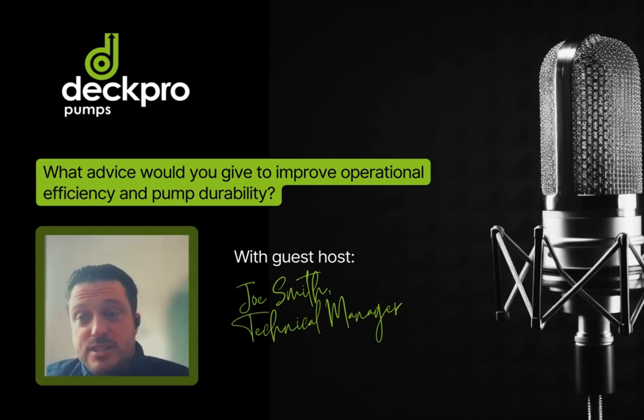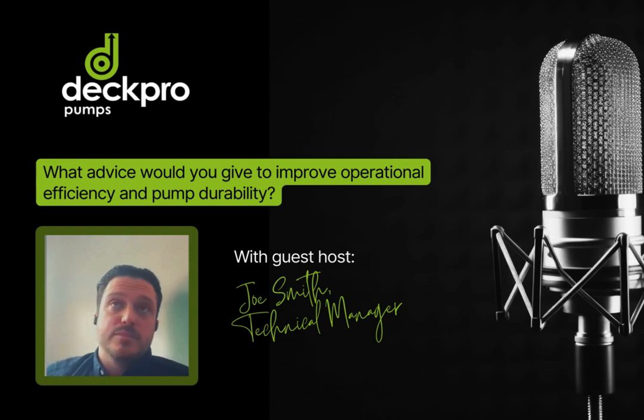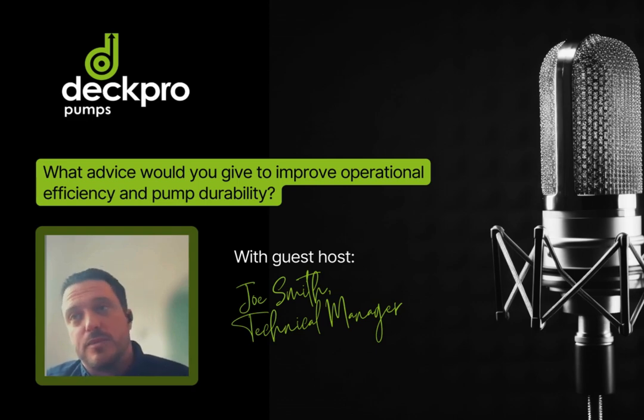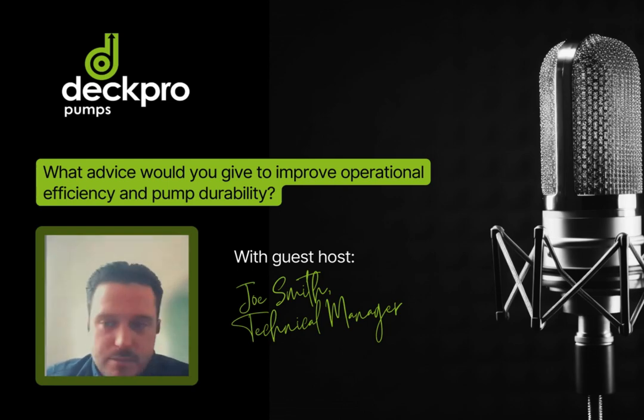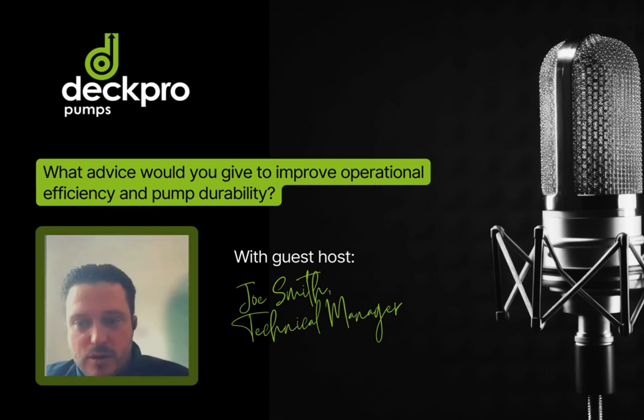Also, small changes in changing fixed speed pumps to inverter driven, but in a small way. So often when we think of inverter drives, we're thinking big. I know like the Grundfos Magna pumps, they've got a little inverter built into them. You can install one of those pretty simply. It's not difficult. They're not too expensive, and you can put that on an auto adapt function, and that'll make energy savings instantly.